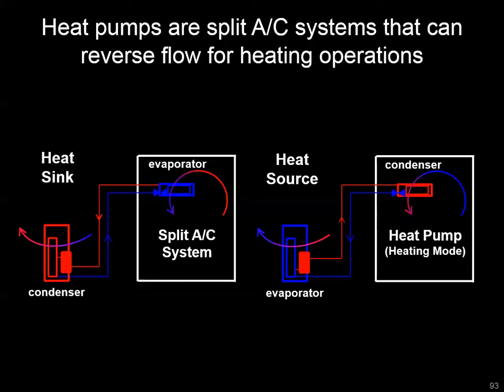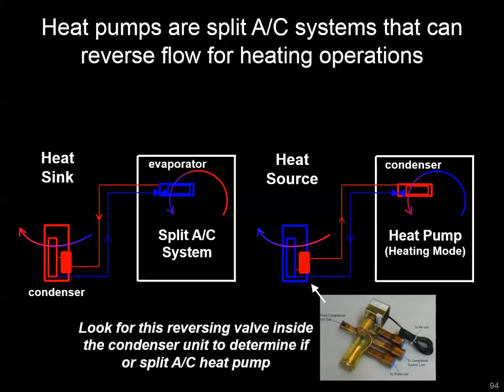There are a few ways to tell if the device you're looking at is a heat pump, because the equipment looks very similar. You can tell from the nameplate if you have some type of heating BTUH, which would indicate a heat pump that can accomplish both heating and cooling. Or you can look down into the condenser assembly and see something called a reversing valve — a manifold valving device that allows reversing of the refrigerant flow while keeping the vapor compression components in the proper order.